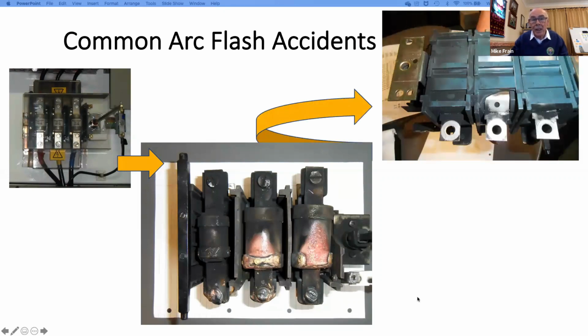When I turn the unit over, I can see what the arcing damage was caused by. It's caused by low-level arcing across the contacts whilst it was on load, and that eventually escalated. And the reason for that was the damage caused by someone forcing oversized fuses into the carriage and cracking the monoblock. I think you can see that, can't you, at the back there. And as you can see on the reverse, that's what's happened. And look at the fuses. Each one of them is a different size to the other. And somebody's purposely forced that fuse into place and cracked it.